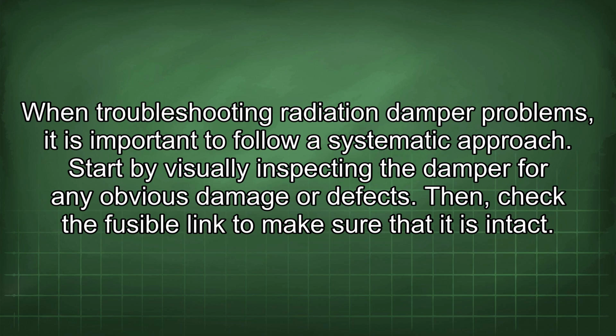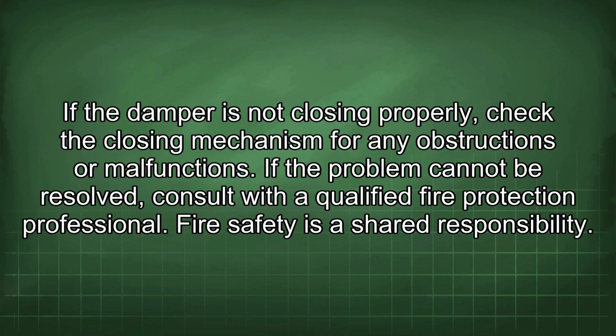When troubleshooting radiation damper problems, it is important to follow a systematic approach. Start by visually inspecting the damper for any obvious damage or defects. Then check the fusible link to make sure that it is intact. If the damper is not closing properly, check the closing mechanism for any obstructions or malfunctions. If the problem cannot be resolved, consult with a qualified fire protection professional.